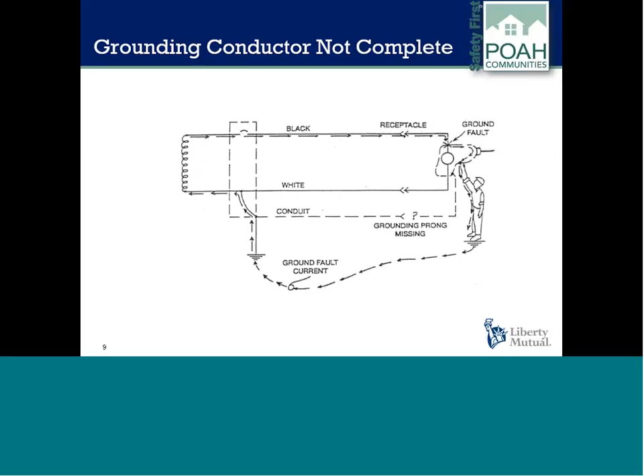Pictured here is another system, which is called protective or equipment grounding. This system is vital for protection of anyone in contact with an electrical device. It consists of an extra wire, normally colored green, extending the length of the circuit and also attached to a metal water pipe or rod buried in the ground. Unlike the system ground, the equipment ground normally does not carry current. It provides a low resistance path to ground whenever the current leaks. This ground can allow another current to flow to the ground to cause an overload and blow a fuse or trip a circuit breaker, which shuts off the current flow and calls attention to the problem.